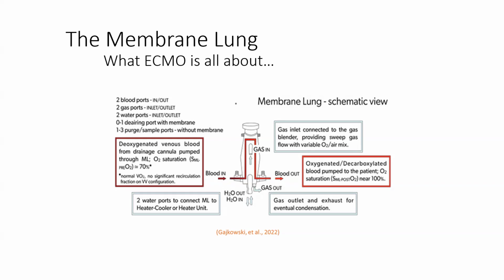There's no carbon dioxide in that. That's going to sweep the CO2 off the blood and add oxygen to the blood, as that gas is going to diffuse through the hollow fibers of that membrane. So what you get out of the bottom of that oxygenator on the arterial side is the blood gas that you're trying to give to that patient. Also, modern oxygenators have the ability to heat and cool the blood. So there's a gas phase, there's two blood phases, a venous and arterial, and then there's a water phase that is a bath that goes around the housing of those fibers that heats and cools your patient.